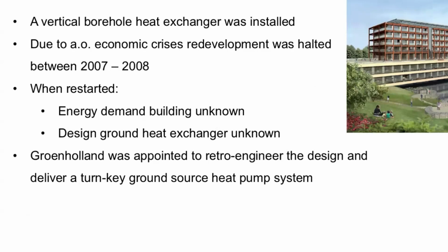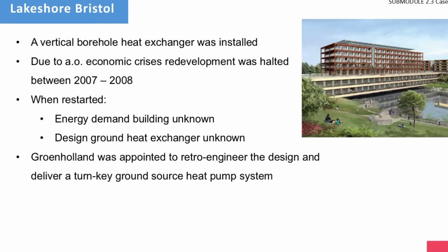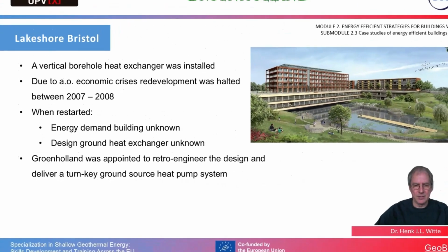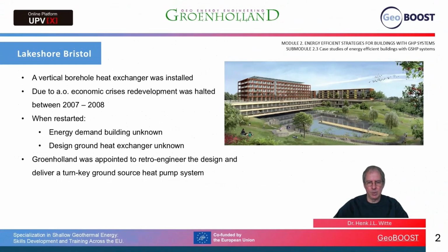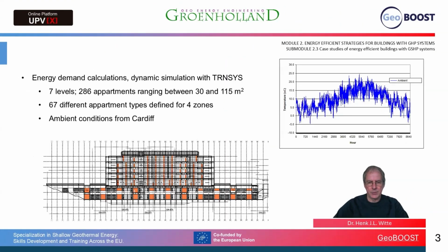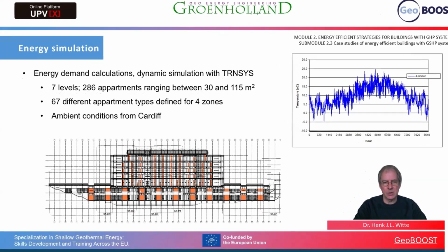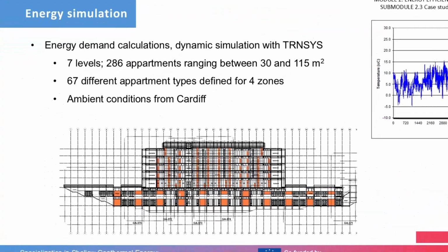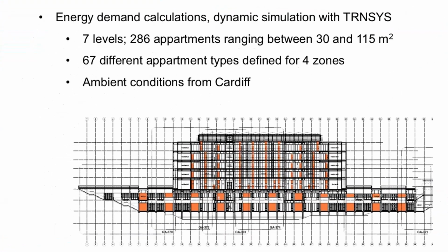Groen-Holland was appointed to retro-engineer the design and deliver a ground source heat pump system that could fit the existing borehole field and still deliver a significant amount of energy to the building. The first step in the process was to do a detailed energy demand calculation based on a dynamic simulation with the TRNSYS program. In total, there are 286 apartments ranging between 30 and 115 square meters, distributed over 7 different levels.